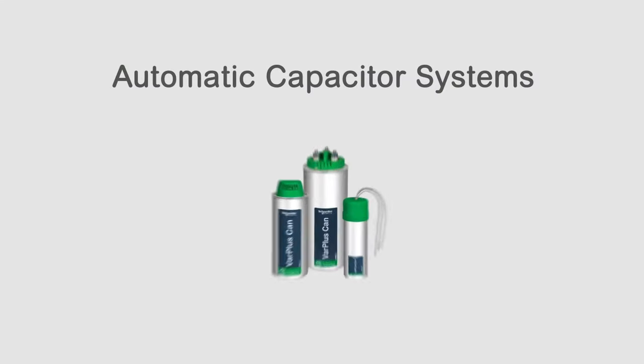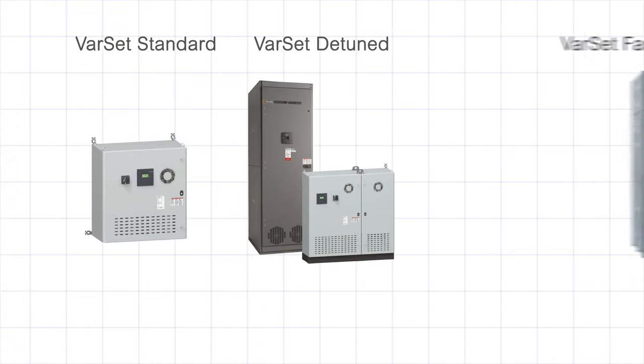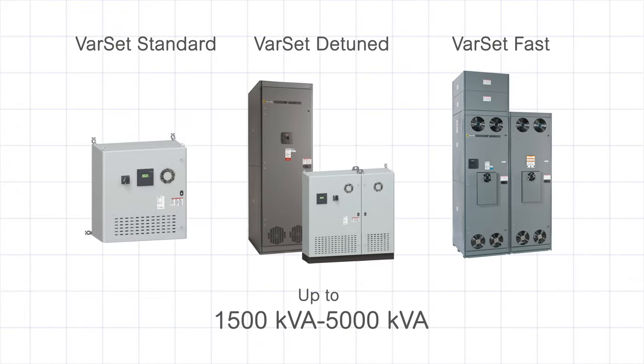The most cost effective way to correct power factor is to use automatic capacitor systems. They're typically installed at the main distribution board or at the MCC's. The Varset system is suited for small and medium-sized networks up to 1,500 kVA and in large installations up to 5,000 kVA.